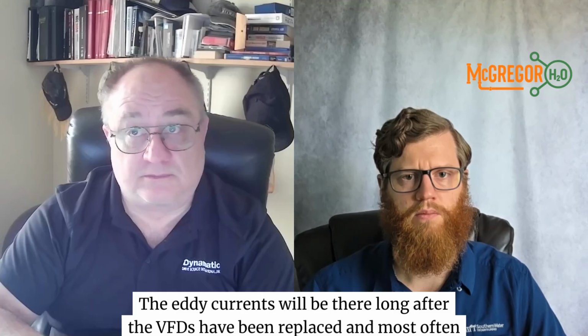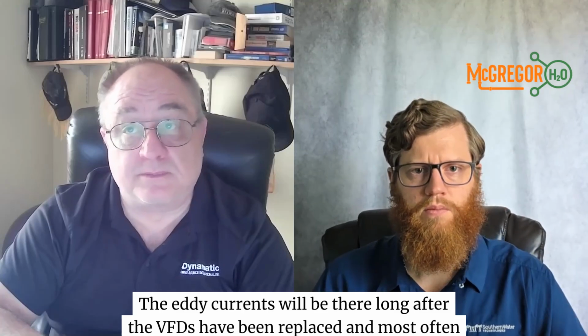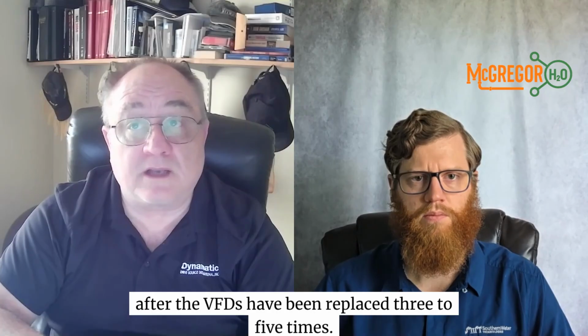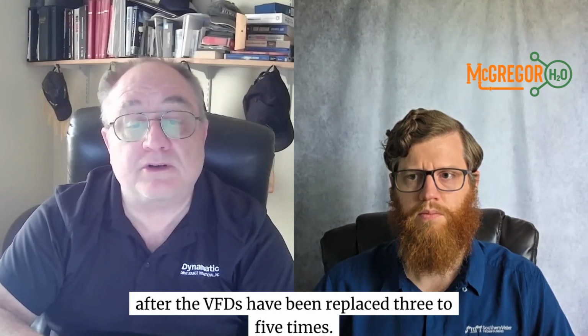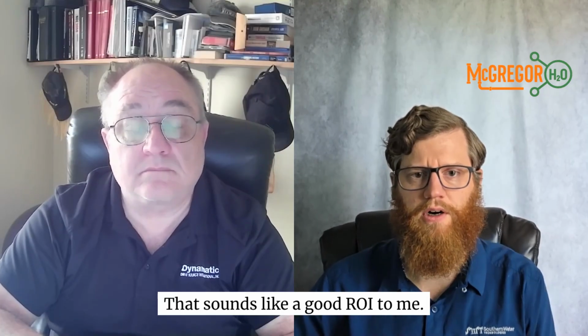The eddy currents will be there long after the VFDs have been replaced, and most often after the VFDs have been replaced 3 to 5 times. That sounds like a good ROI to me.